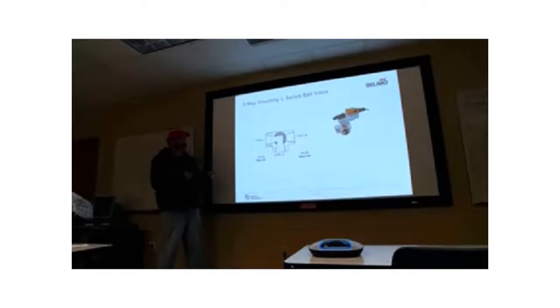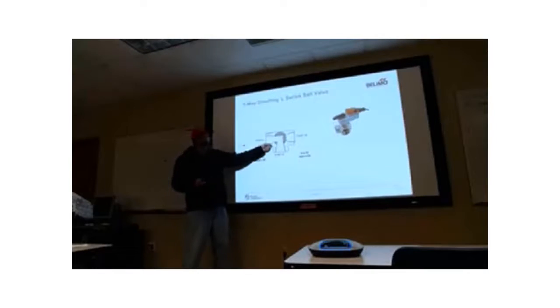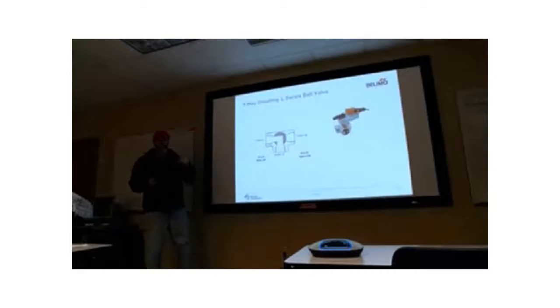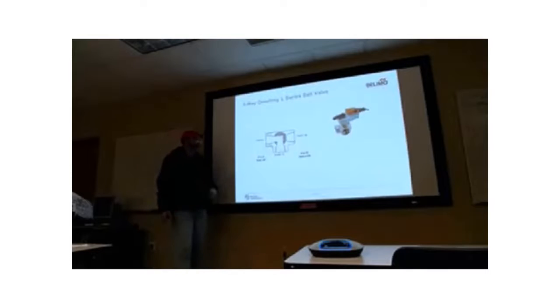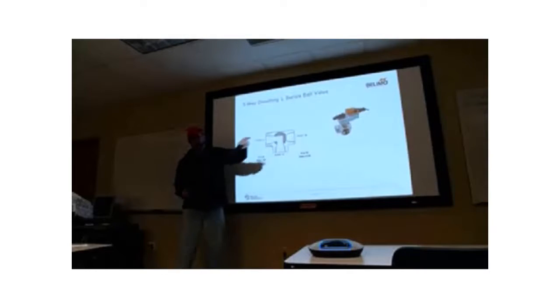They're actually a little bit less expensive in some cases. But you do not want to use this type of valve for what we call proportional control of a coil. You only want to use it if you want to switch streams, right? Through a bypass or something like that. Now again, look, port B is common, right? And it comes in, and it goes either that way or it goes that way.